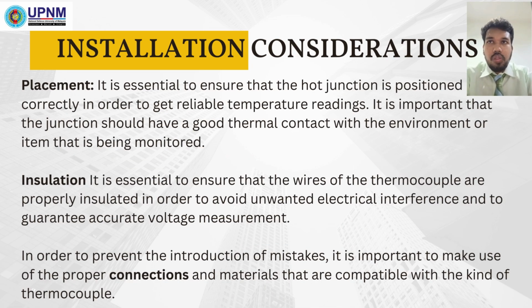Next slide is about considerations of thermocouple placement, insulation, and connection. For the placement, ensure the hot junction is correctly positioned for reliable temperature reading, and maintain good thermal contact with the environment. For the insulation, we must properly insulate the thermocouple wires to prevent electrical interference and ensure accurate voltage measurement. For the connection and the material, you must use appropriate connections and material compatible with the type of thermocouple, and prevent the introduction of error through the proper selection and use of the material.